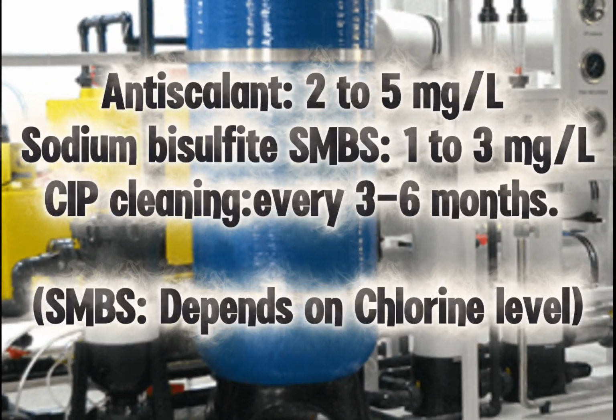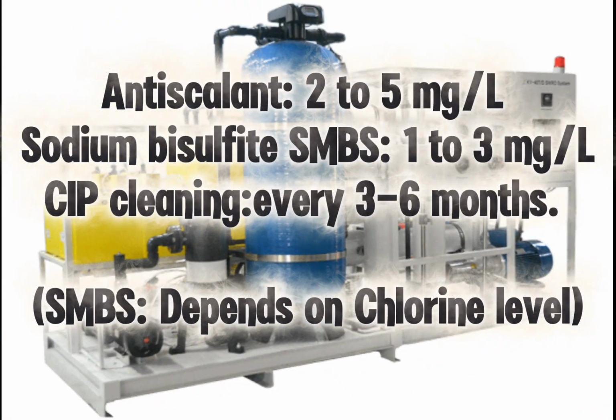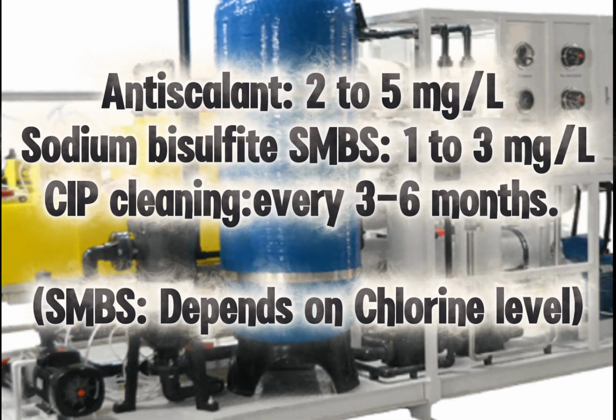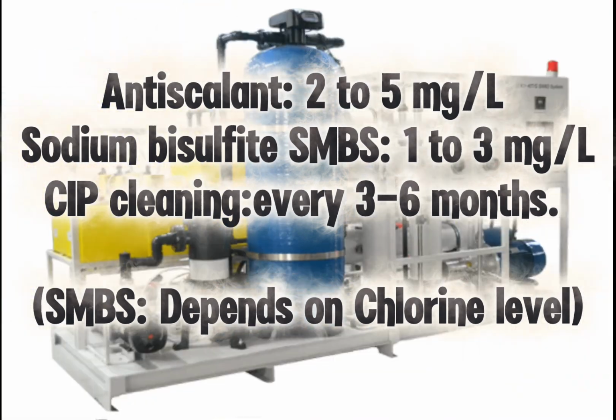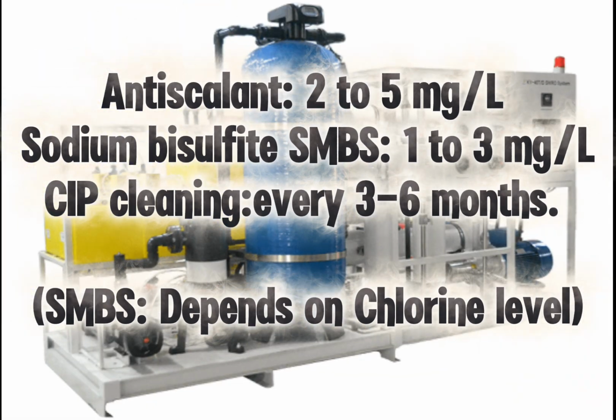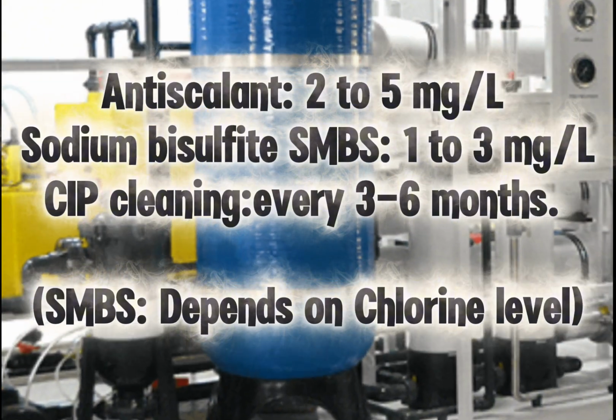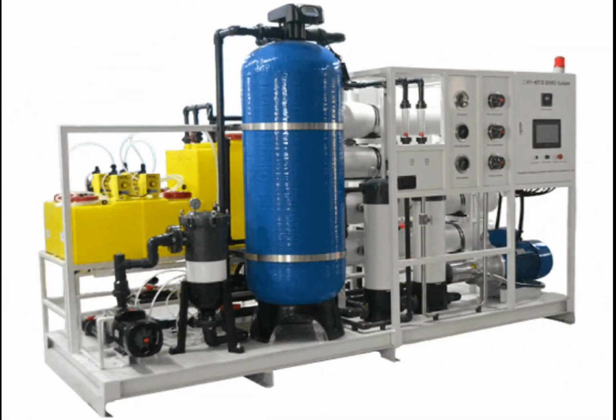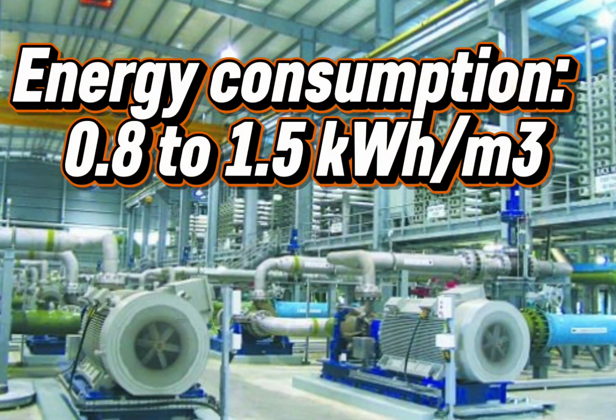Chemical dosing was equally important, with antiscalant added at 2 to 5 mg per liter and sodium bisulfite at 1 to 3 mg per liter to remove chlorine, while CIP cleaning is generally required every 3 to 6 months. Energy consumption of the system typically ranges from 0.8 to 1.5 kWh per cubic meter.